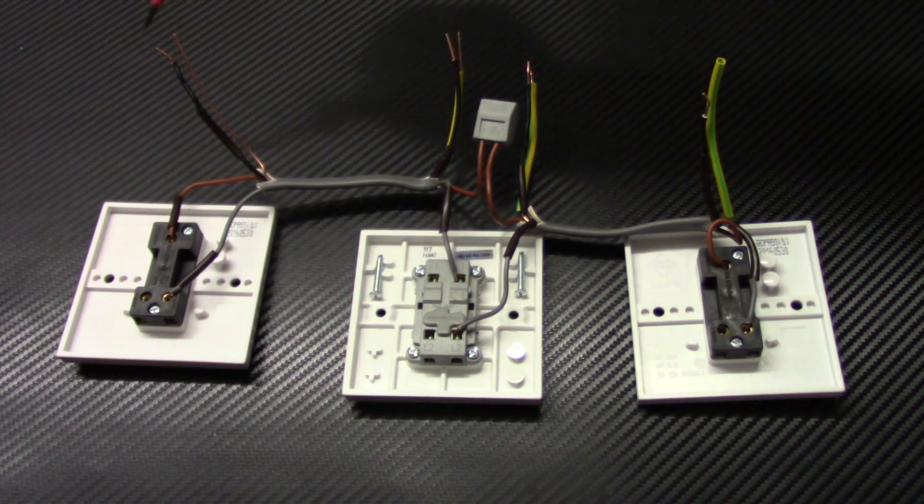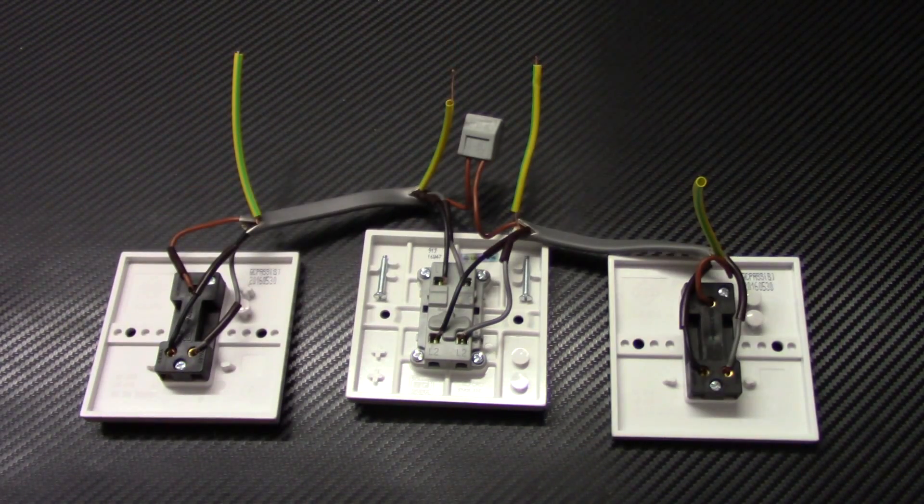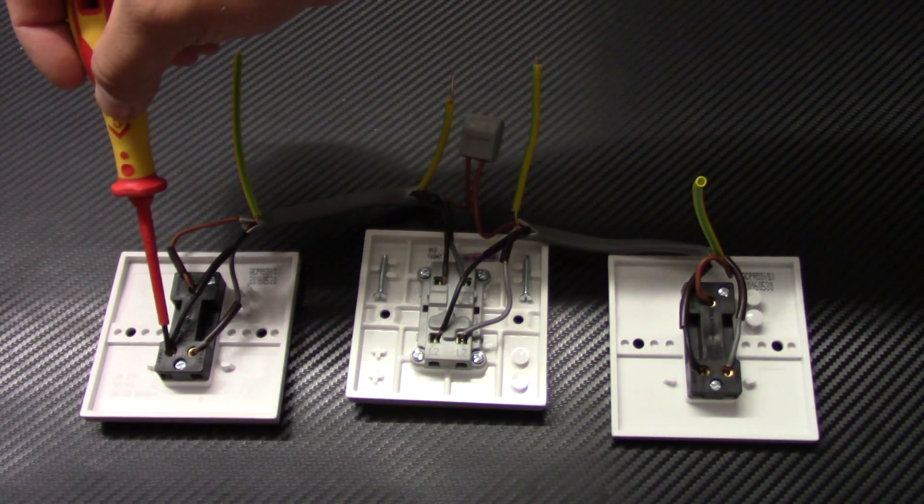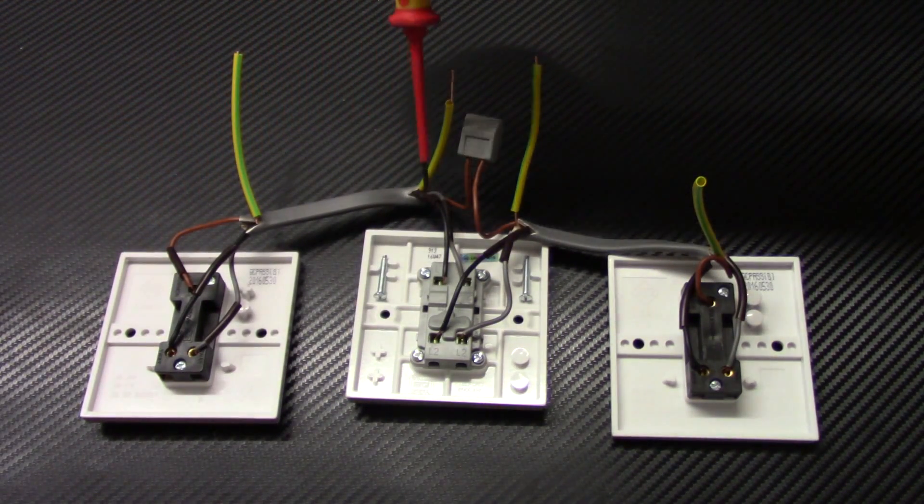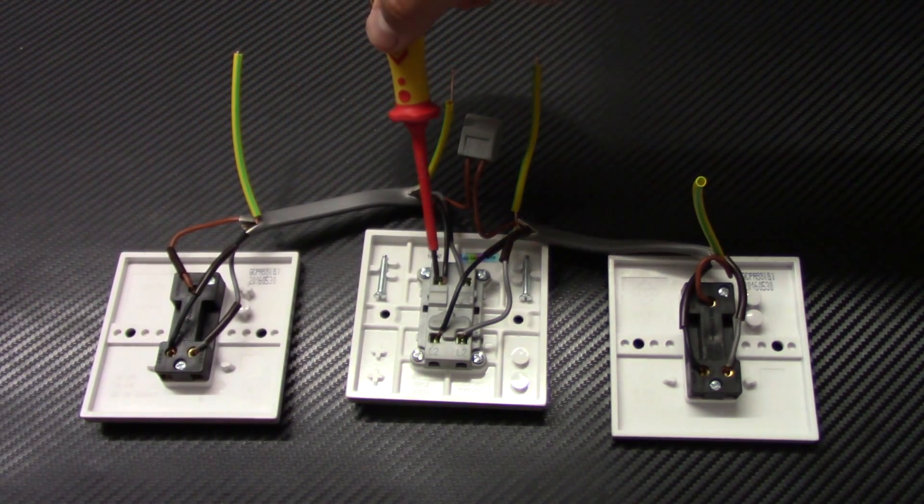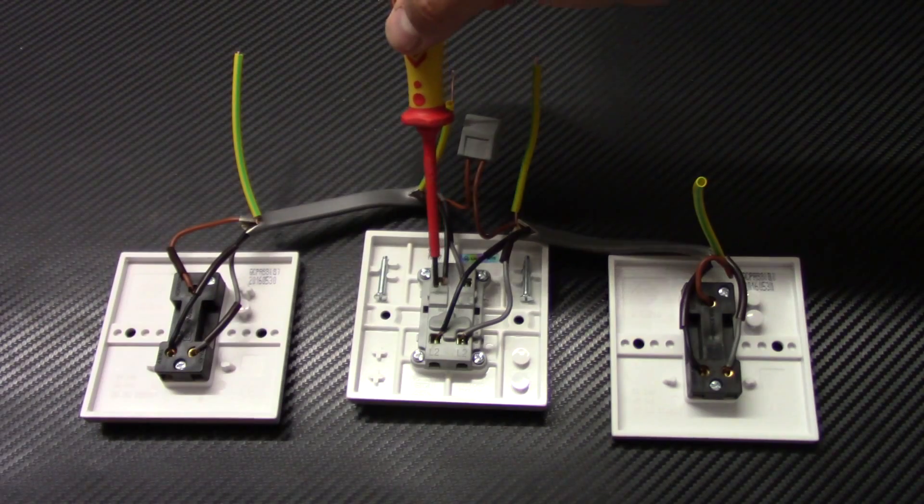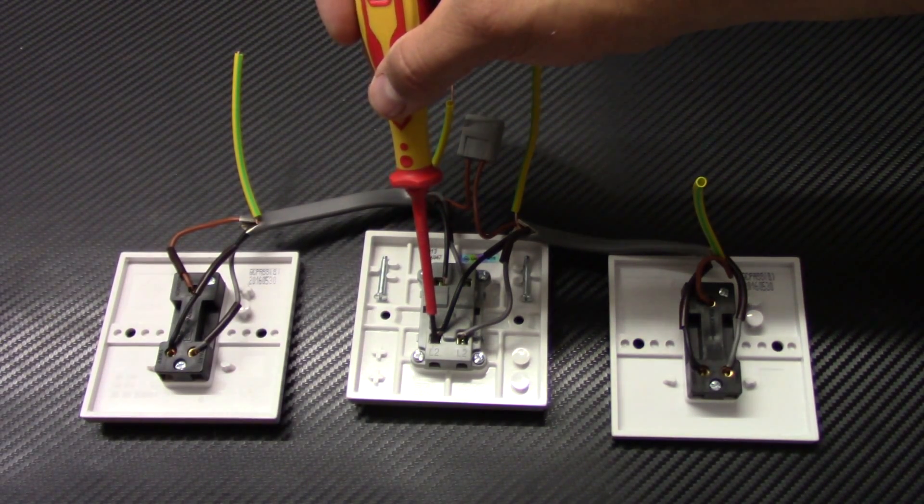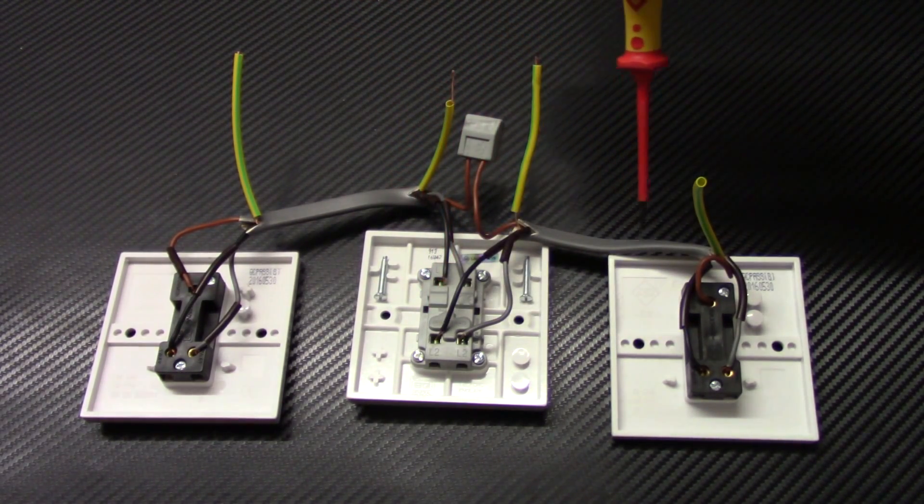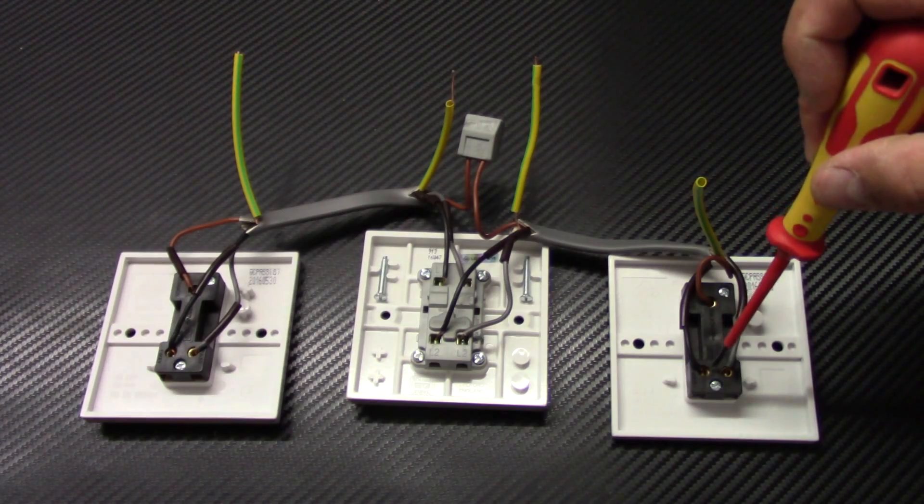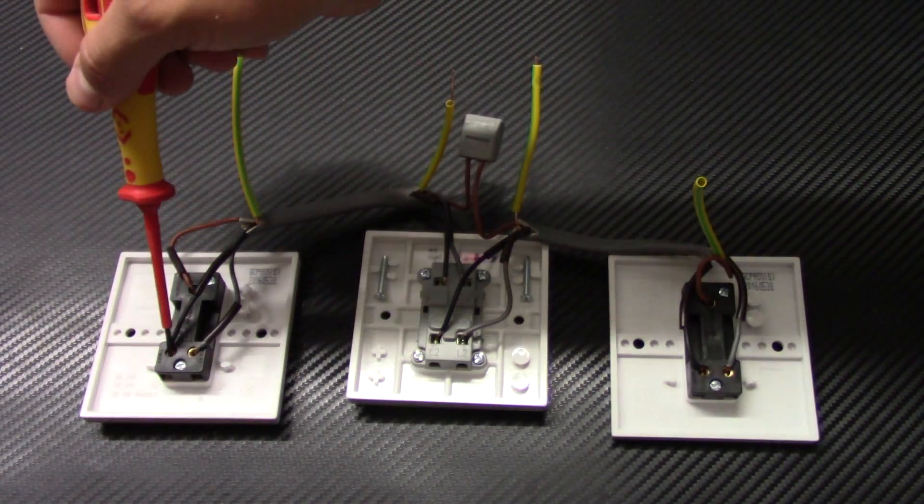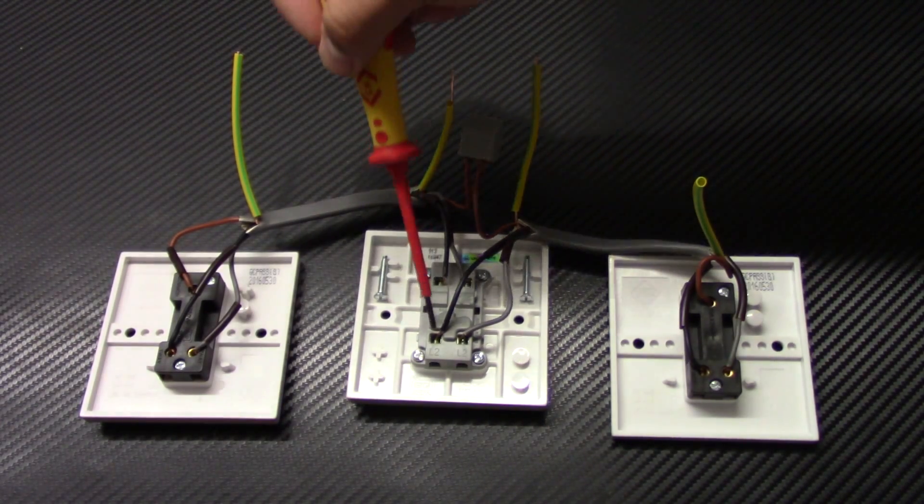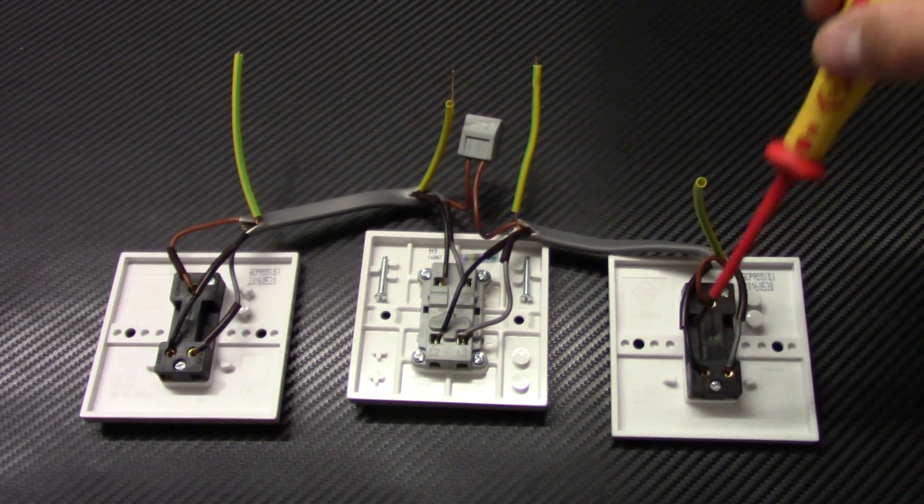Now let's connect the black wire. The black wire is coming from the L1 or one-way in two-way switch. Then going to intermediate switch to L1. Then on the opposite from L2 to another two-way switch to L1. So L1, L1, L2, L1.